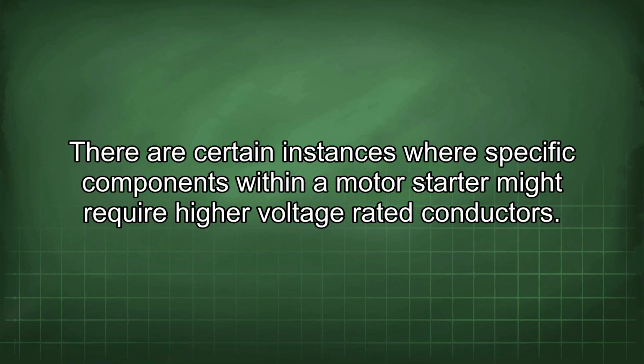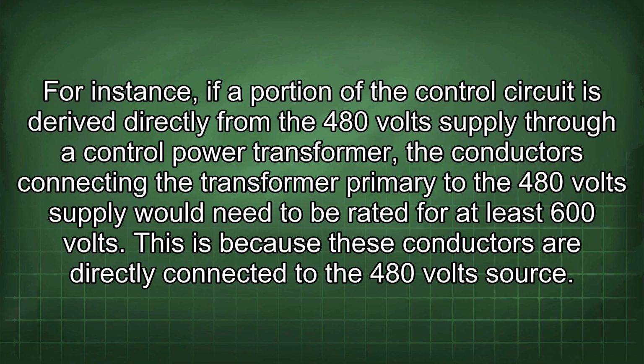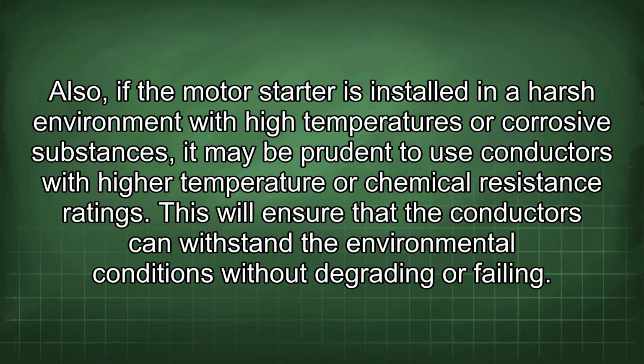There are certain instances where specific components within a motor starter might require higher voltage rated conductors. For instance, if a portion of the control circuit is derived directly from the 480 volt supply through a control power transformer, the conductors connecting the transformer primary to the 480 volt supply would need to be rated for at least 600 volts. This is because these conductors are directly connected to the 480 volt source. Also, if the motor starter is installed in a harsh environment with high temperatures or corrosive substances, it may be prudent to use conductors with high temperature or chemical resistance ratings. This will ensure that the conductors can withstand the environmental conditions without degrading or failing.